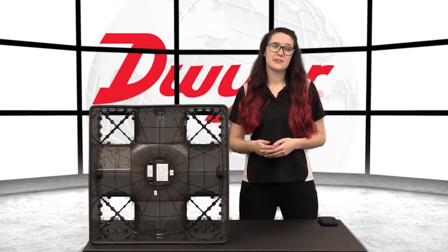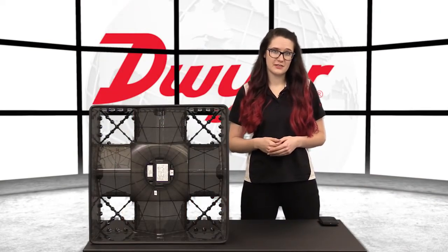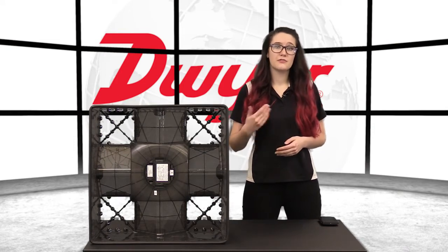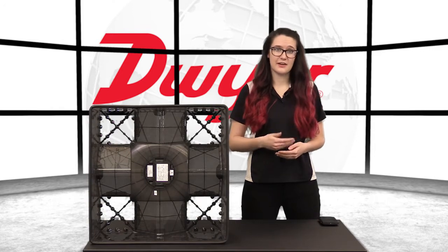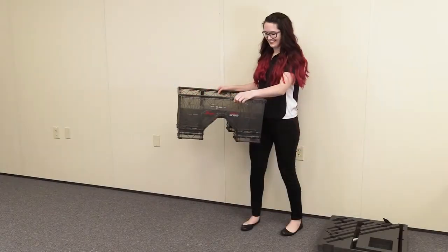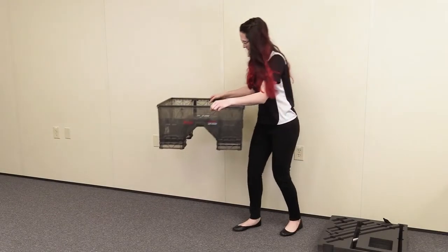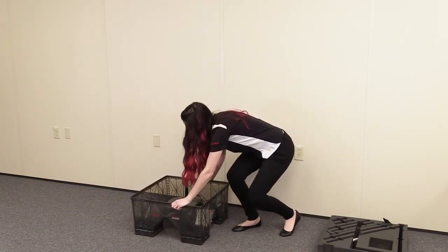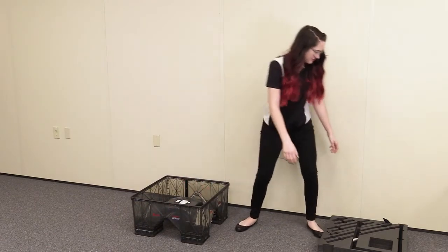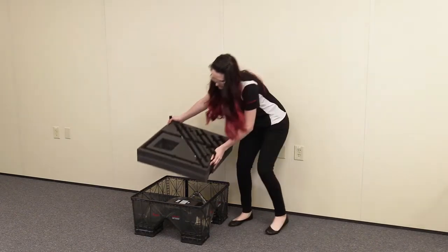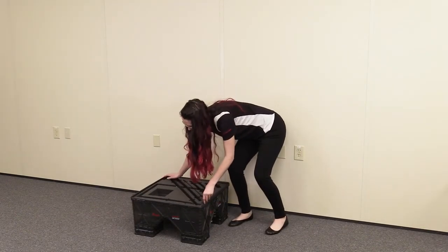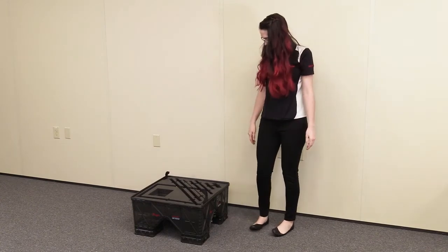It's important to zero your hood in order to ensure accurate measurements. We recommend you zero your hood before you start balancing for the day, as well as when switching between ceiling and sidewall air measurements. To zero for ceiling diffuser readings, place your hood on the ground so all 4 pitot arrays are making contact with the floor. Place the foam insert from the carrying case or another flat object over the top of the hood to restrict airflow from entering the hood.